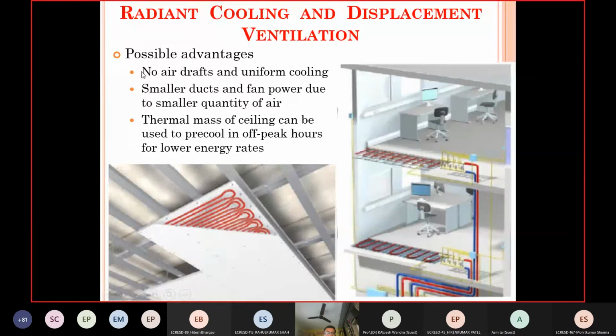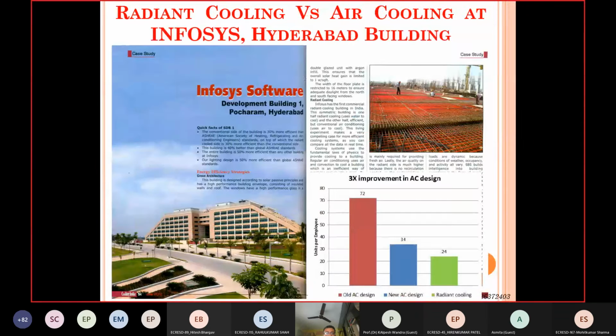So radiant cooling, again, other possible advantages: no air drafts and uniform cooling, smaller ducts, because you are supplying very limited air for providing fresh air only. So the ducts could be smaller, and the fan power due to that would be smaller. And the thermal mass of the ceiling can be used to pre-cool in off-peak hours for lower energy rates. So energy storage is also one of the possible advantages of this kind of system.